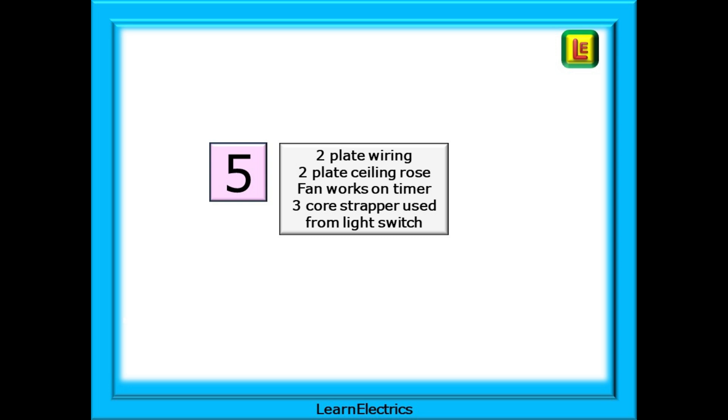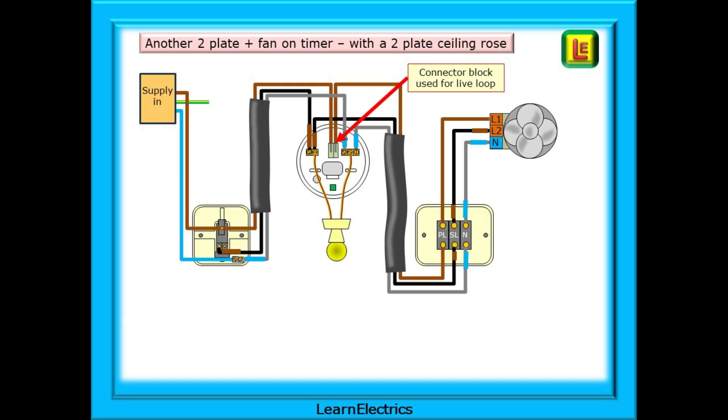What can we do if it's a two plate lighting circuit and it's not possible to change the existing two plate ceiling rose? If we can run a new three core and earth strapper cable from the light switch to the ceiling rose we now need somewhere to connect the permanent line. We can use a connector block, WAGOs or similar to do this.